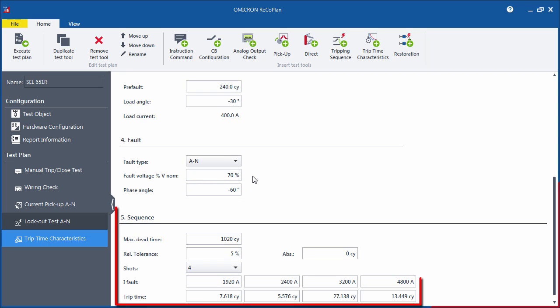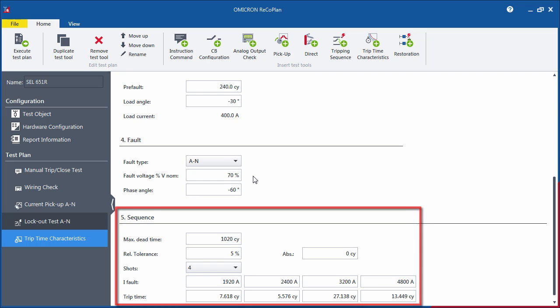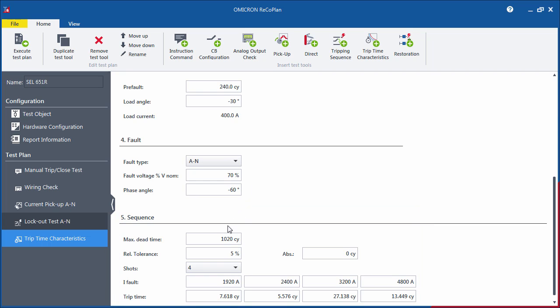In the Sequence section, you can define the test shots. Start with the maximum dead time, which has to be longer than the highest open interval time defined in the recloser control settings. This is the maximum time that the software will wait for a closed signal during each cycle.